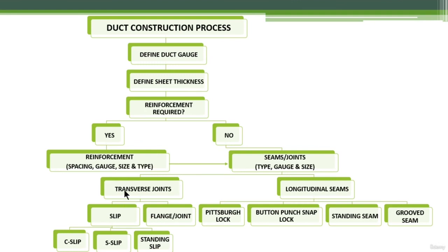On the longitudinal seams, there are four main types: the Pittsburgh lock, the button punch snap lock, the standing seam, and the groove seam. In almost 90 percent of cases, the Pittsburgh lock is the preferred method for longitudinal seams. Similarly, for transverse joints, the C-slip and S-slip are almost always used.